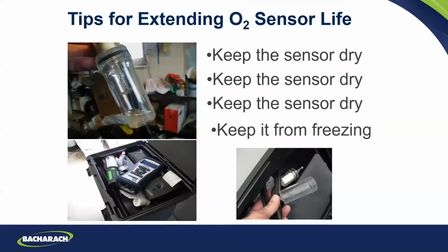One of the other questions we all get is, do I have to take this in at night? You don't have to, but if you looked in specs of any of our instruments, it probably says you can take these down to 10 degrees. But CO sensors and oxygen sensors are electrochemical sensors, so it's not water in there, but they will freeze at some point, especially if there's moisture in them. By principles of contraction and expansion, it'll pop that sensor. So you want to bring it in when it starts getting cold, about the mid-20s.